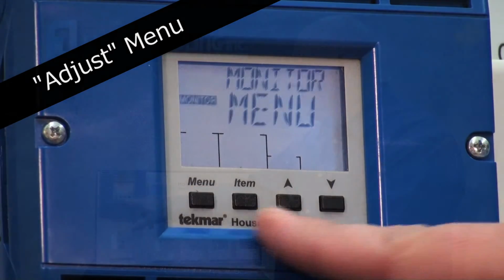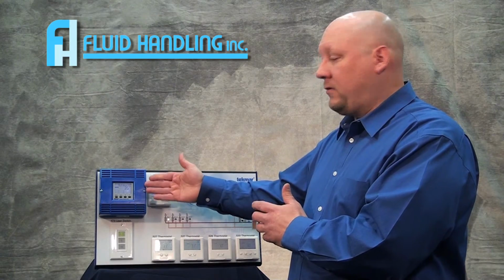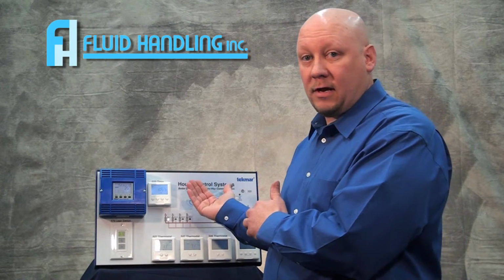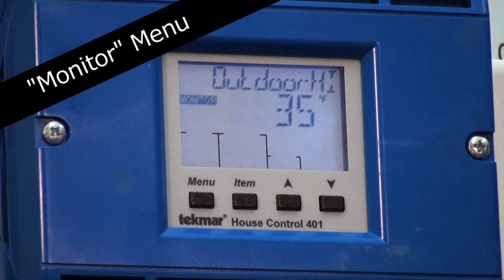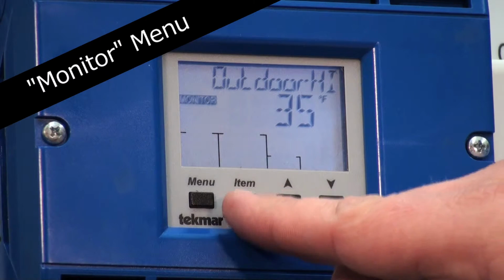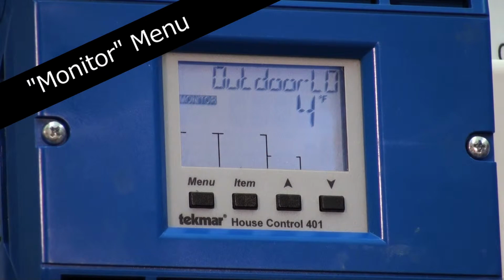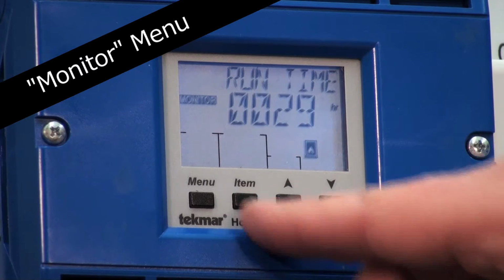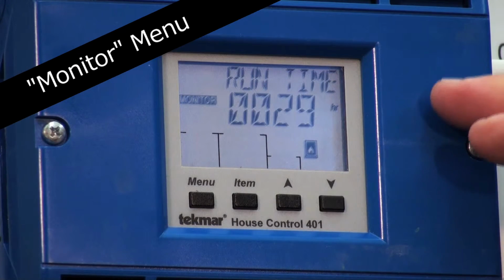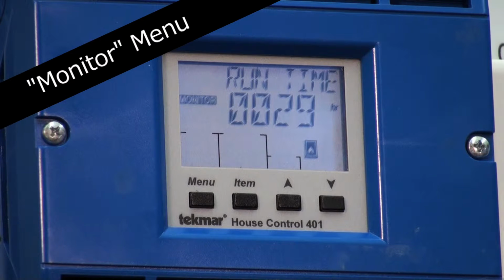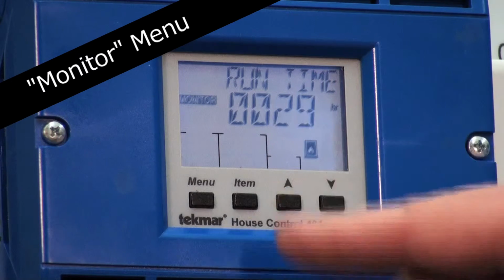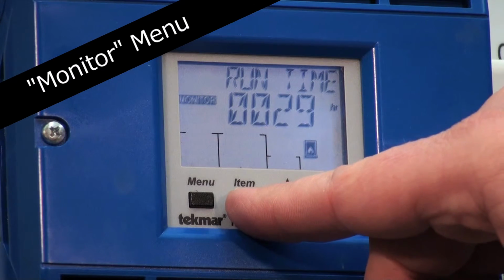Pressing menu again is now going to take us to the monitor screen. So here we're showing the highest outdoor temperature that the outdoor sensor has seen. In this case, for our demo, has been 35 degrees. Item again is going to show you the outdoor low. It had seen a temperature of 4 degrees outside. It's also going to show you the run hours of the boiler. How many exact hours has the boiler been on heating the home? And in this case, 29 hours.